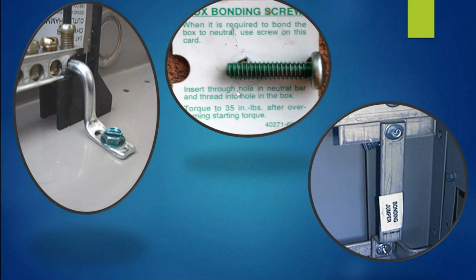And of course, a lot of times we see a simple green screw. And you notice that it has torquing values on here. That gives me the opportunity at this point to talk a little bit about torquing. Now, torquing is a requirement of the National Electrical Code. Now, it's surfaced as a new section in the 2017 code, 110.14(D).